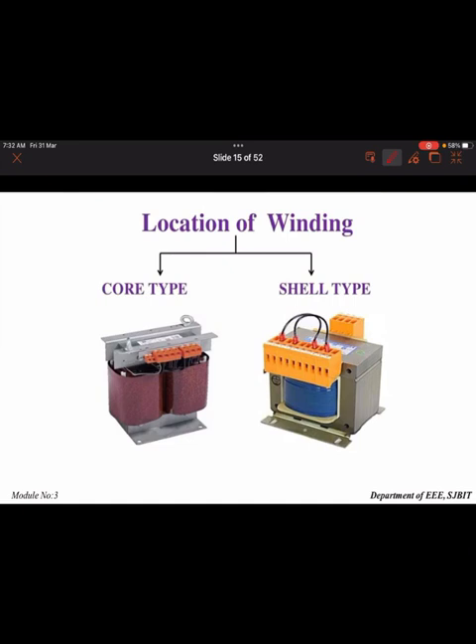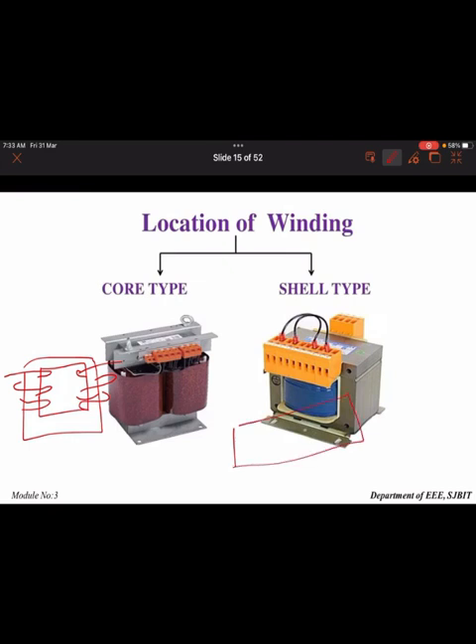Depending on the construction, transformers can be divided into core type and shell type, based on how the winding is placed. In the core type, the core is surrounded by the winding. In the shell type, the winding is placed inside and surrounded by the core. The core type has only one magnetic circuit path, while the shell type has two magnetic circuit paths. This is the main difference between core type and shell type.